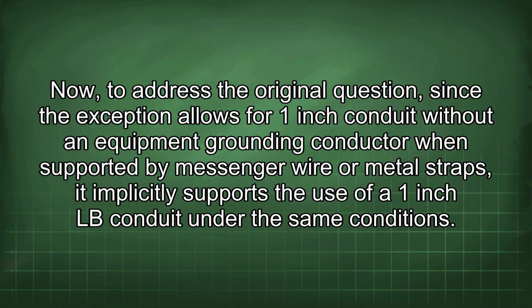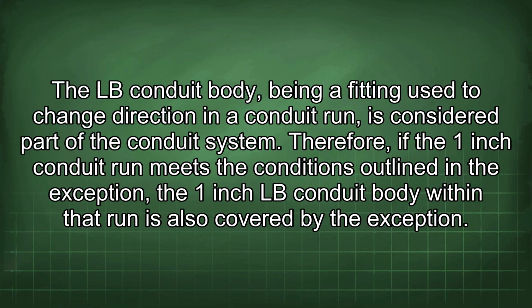Now, to address the original question, since the exception allows for 1-inch conduit without an equipment grounding conductor when supported by messenger wire or metal straps, it implicitly supports the use of a 1-inch LB conduit under the same conditions. The LB conduit body, being a fitting used to change direction in a conduit run, is considered part of the conduit system. Therefore, if the 1-inch conduit run meets the conditions outlined in the exception, the 1-inch LB conduit body within that run is also covered by the exception.